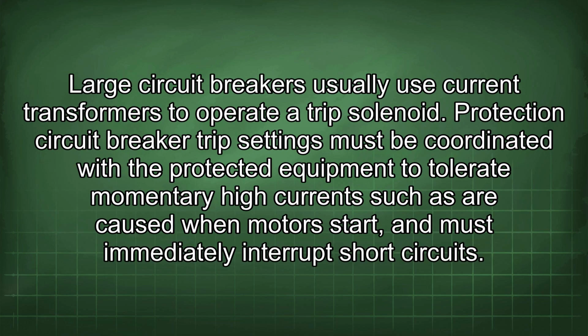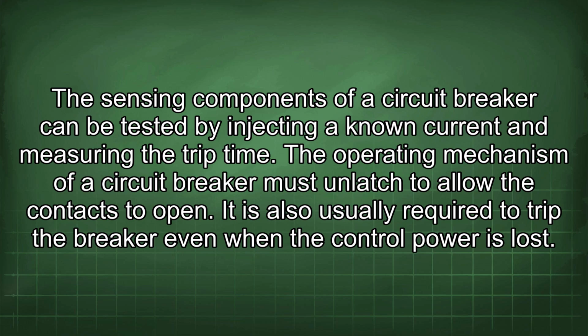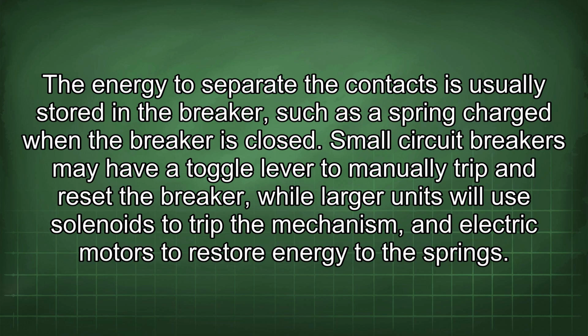Large circuit breakers usually use current transformers to operate a trip solenoid. Protection circuit breaker trip settings must be coordinated with the protected equipment to tolerate momentary high currents such as are caused when motors start, and must immediately interrupt short circuits. The sensing components of a circuit breaker can be tested by injecting a known current and measuring the trip time. The operating mechanism of a circuit breaker must unlatch to allow the contacts to open. It is also usually required to trip the breaker even when the control power is lost. The energy to separate the contacts is usually stored in the breaker, such as a spring charged when the breaker is closed. Small circuit breakers may have a toggle lever to manually trip and reset the breaker, while larger units will use solenoids to trip the mechanism and electric motors to restore energy to the springs.